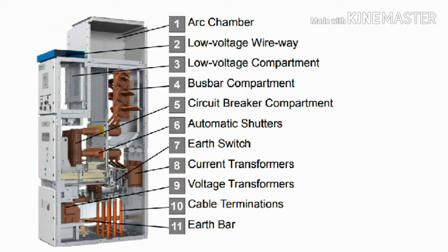Sixth is the automatic shutter, which is placed at the circuit breaker terminal connections. Whenever we insert the circuit breaker, the automatic shutter will open and close. Seventh is the earth switch. The earth switch helps so that whenever we isolate the circuit breaker from the switchgear, the earth switch closes and it prevents the auto false closing of the circuit breaker.